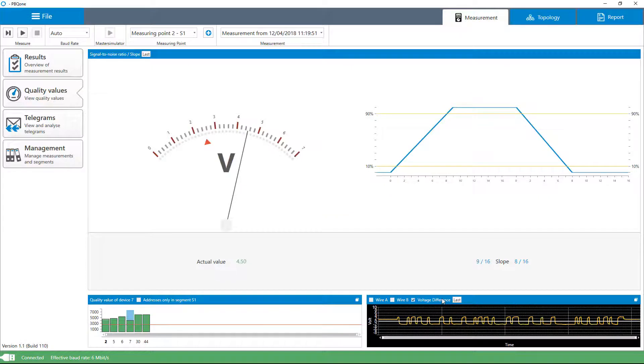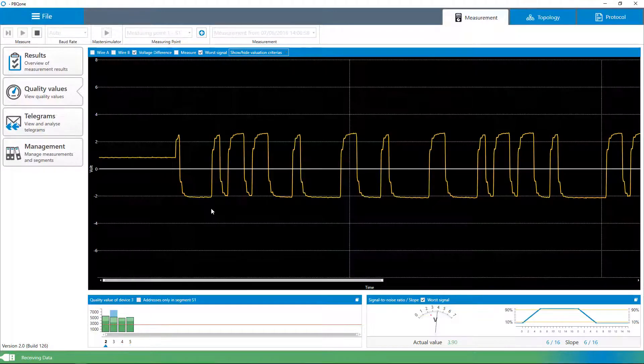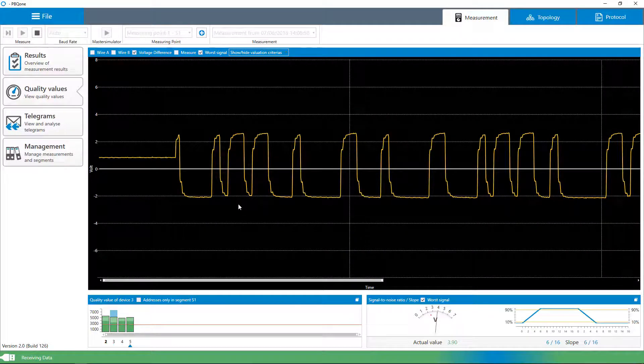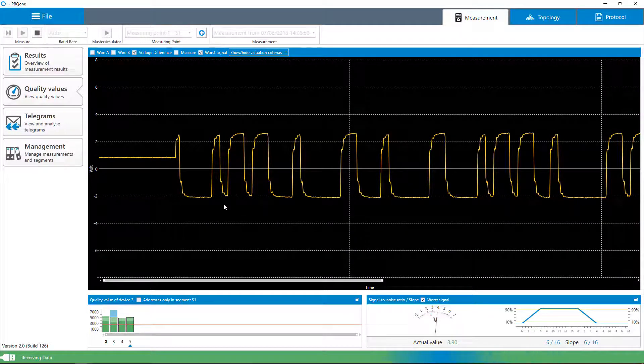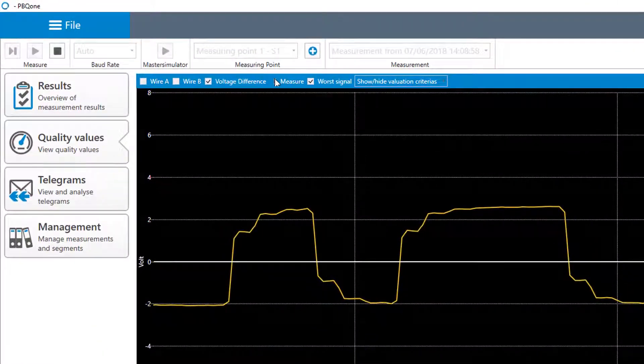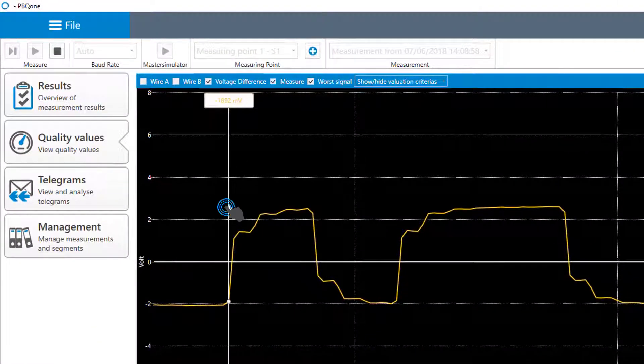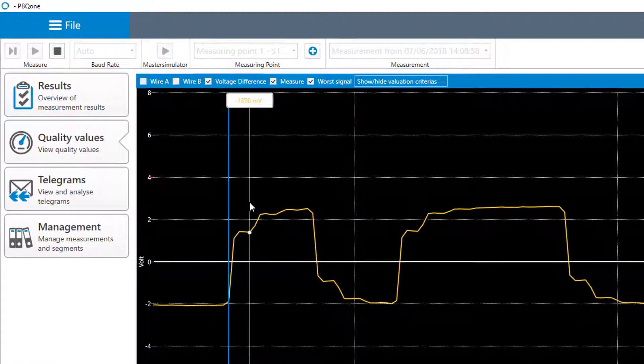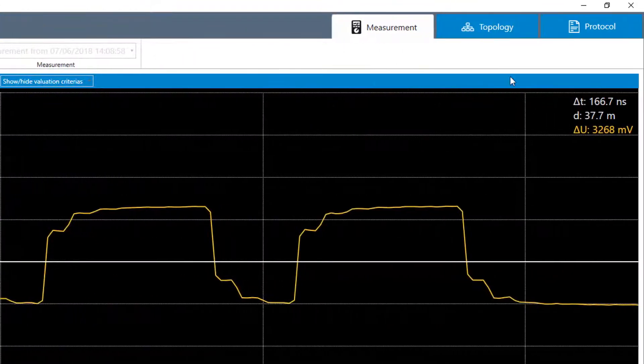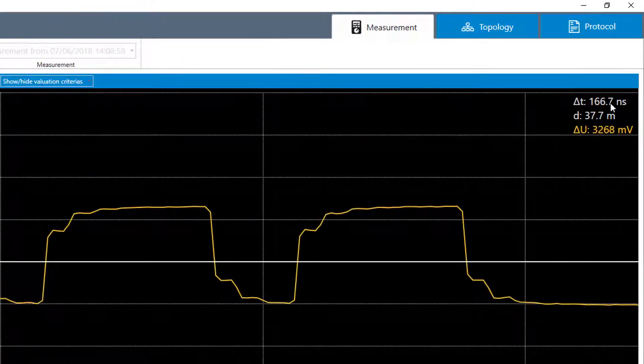In addition, a display of the disturbance-free voltage range and edge steepness and an oscilloscope screen are available for detailed evaluation. The fault is located by two cursors which measure the time interval to a reflecting point and thus the cable length between center and fault location.